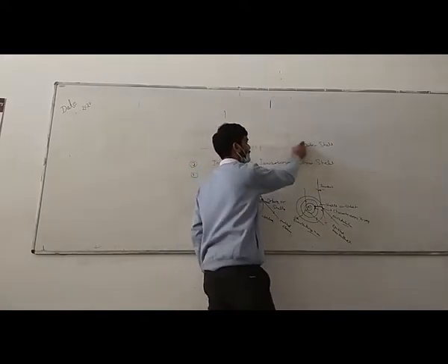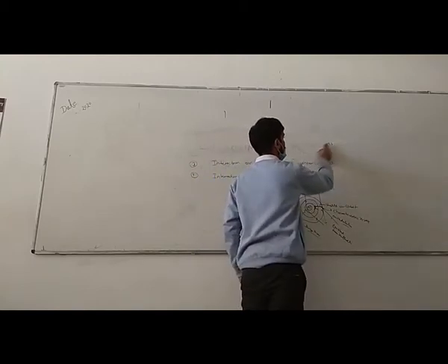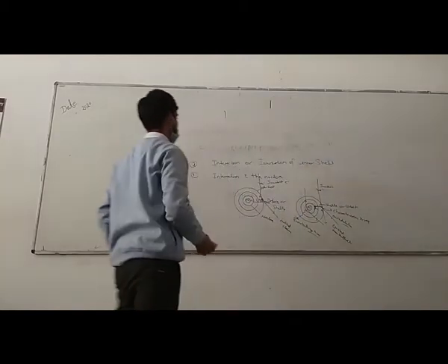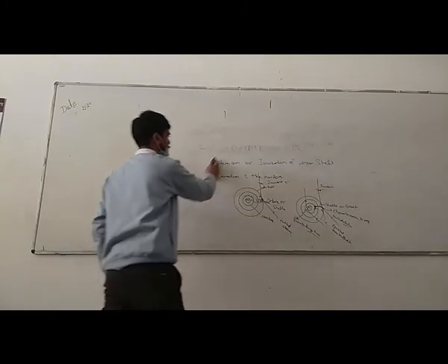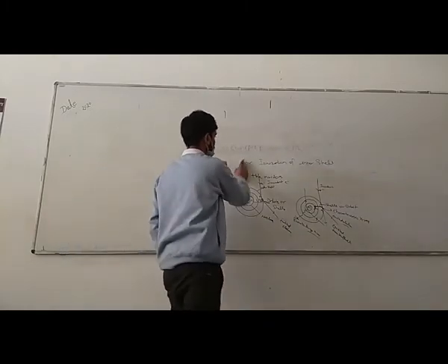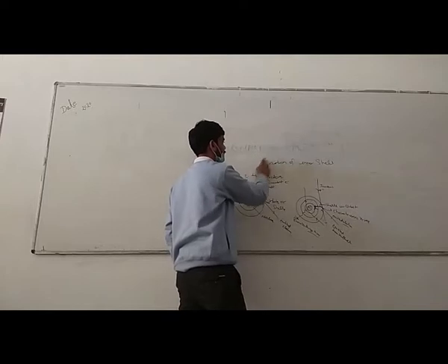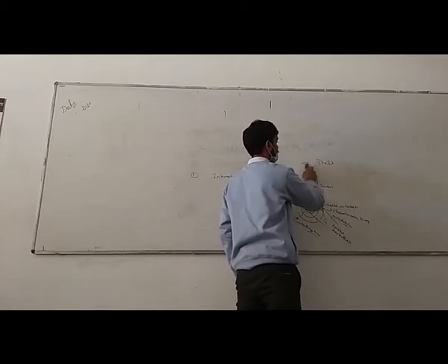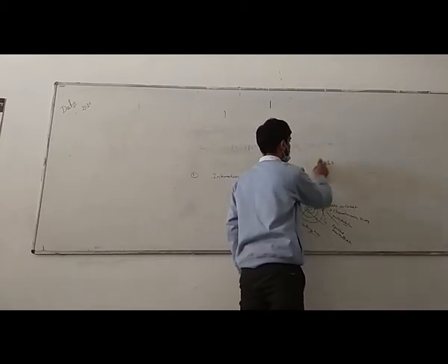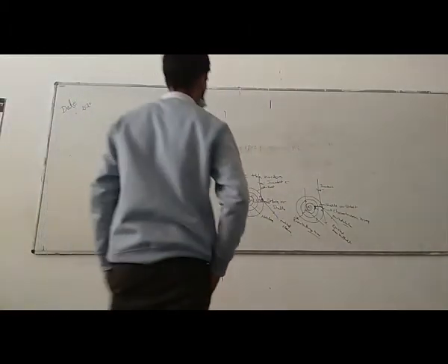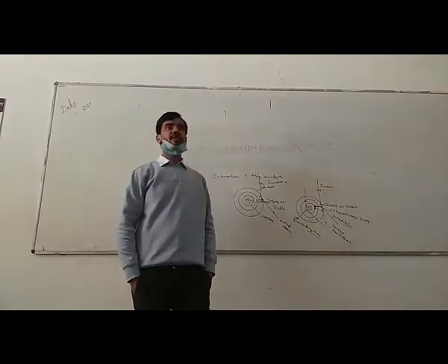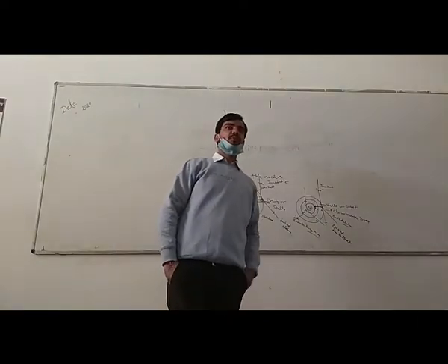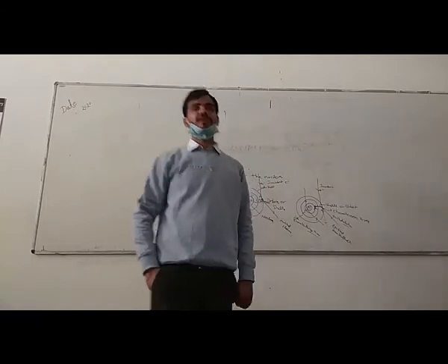The third requirement is high voltage, a high potential applied between cathode and anode to produce the electron. Fourth requirement is vacuum. Fifth requirement is tube insert and housing.